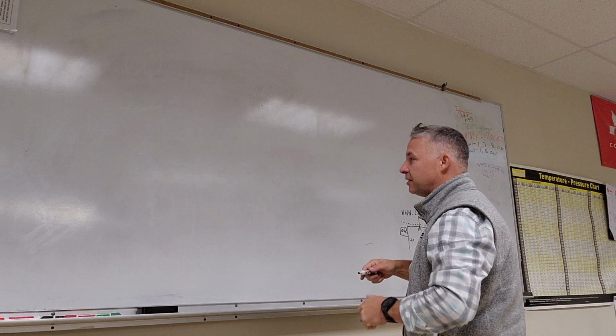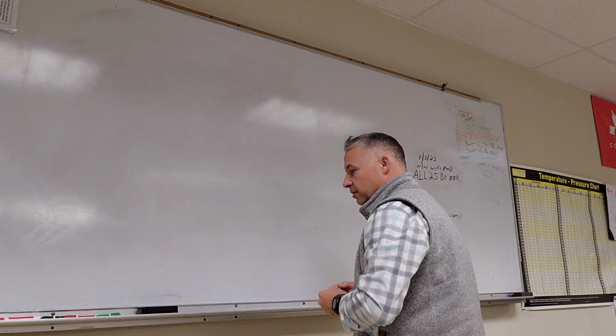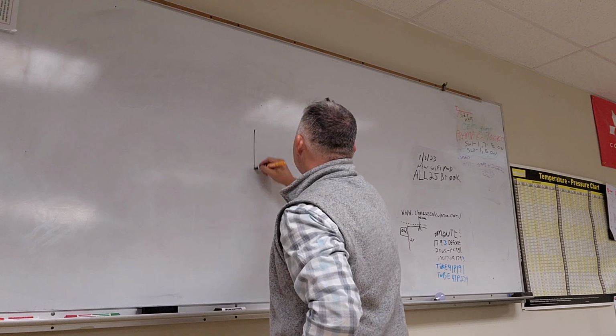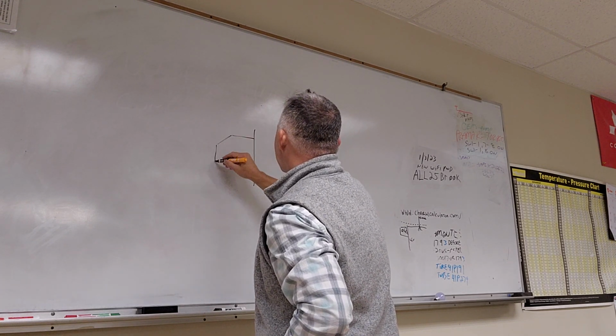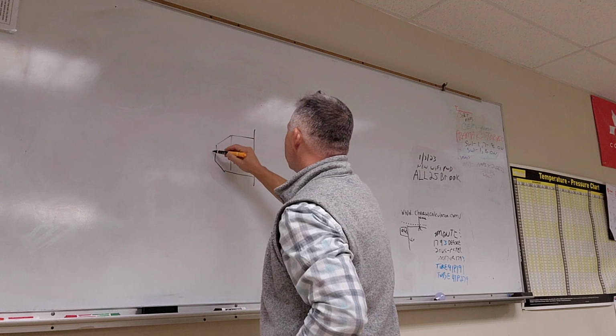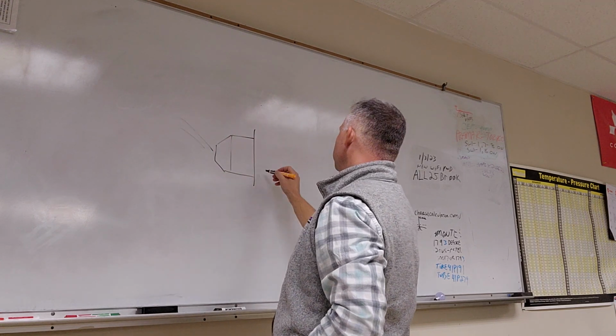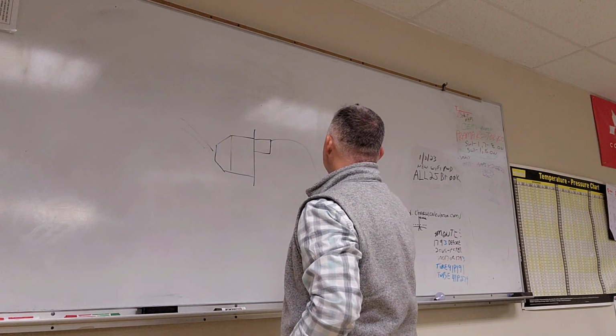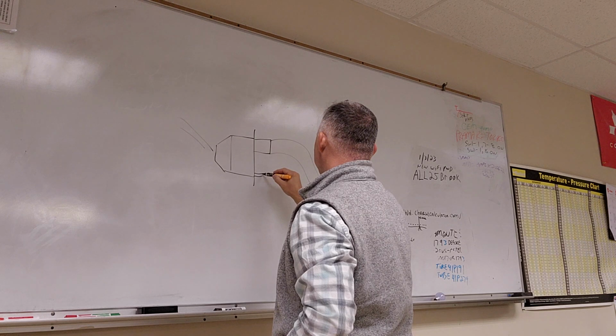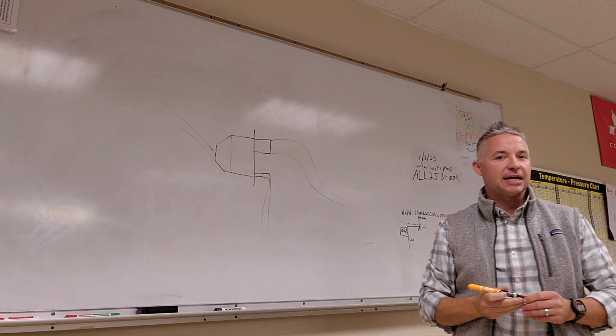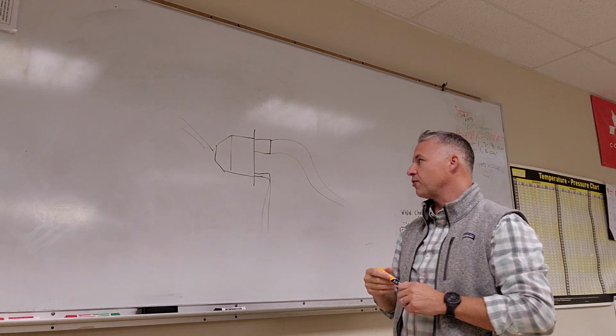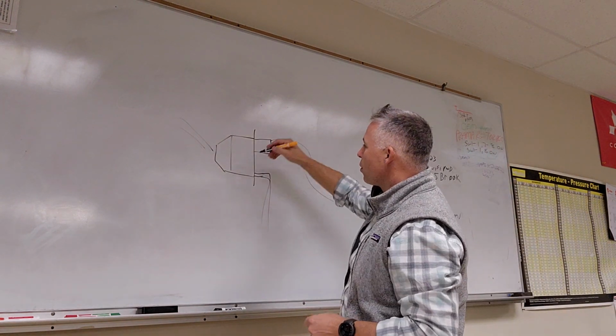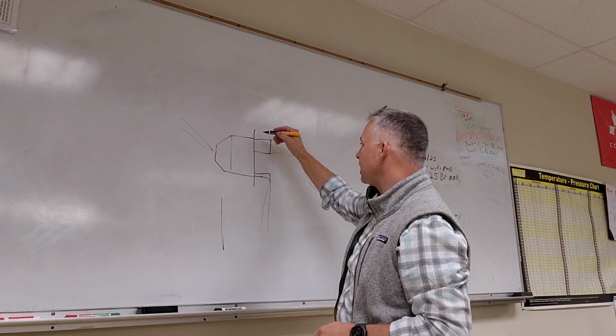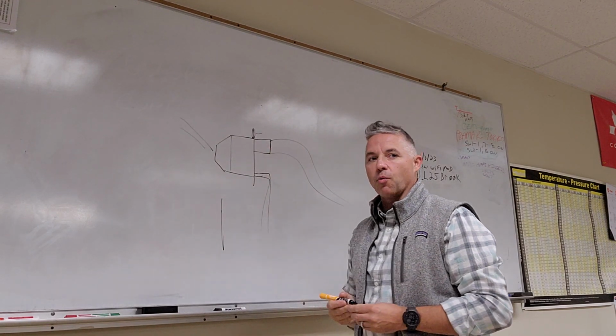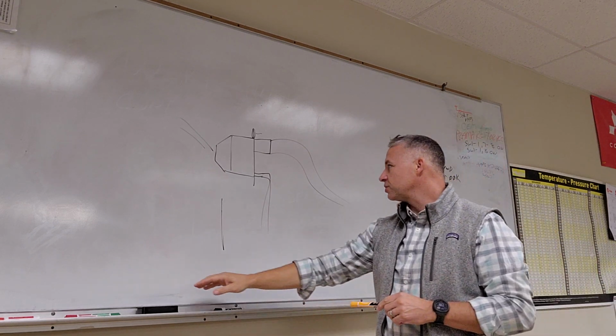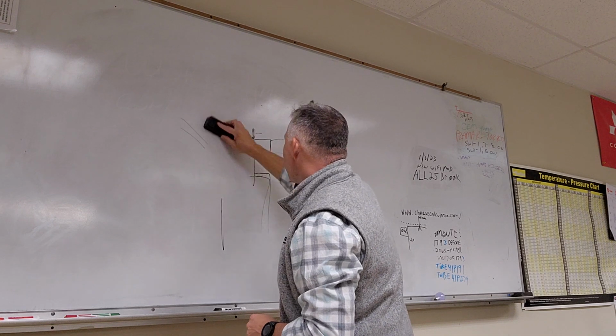There's two types of steam nozzles out there. There's an old one that's mounted on the ductwork, and inside it just kind of looks like this, right? And the steam does this. This has to be pitched on an angle because of the way that the steam hose attaches to it like this, and then on the bottom there's another small piece that's a drain. Because you're going to end up with condensation inside that nozzle. And that condensation's got to drain out. So pitch is important. Ductwork is usually plumb on the side. So sometimes when we put the screw in there, we might put a couple of washers just to make sure that's pitched. The newer style ones that are being installed are an actual tube.